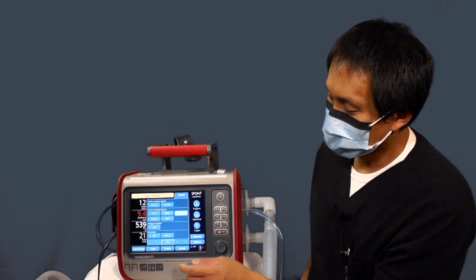We're going to go under volume ventilation mode. On here you do have APV CMV and APV SIMV. APV CMV is essentially VC AC on this ventilator. However, you can get it set up so it's close to a PRVC setting by using your alarm limits. The prefix APV denotes having auto flow, which essentially adjusts the flow that's in the circuit, and your rise time. So you do not need to set those if you're using these two modes.